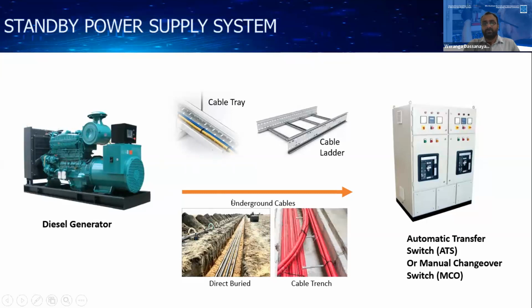same as before in the medium voltage system, the cable may go through a cable tray, cable ladder, or an underground cable. Then it comes to an automatic transfer switch or manual changeover switch. I think if you have visited some larger scale buildings, you can see this kind of installation. Mainly, most of those buildings have a room called the electrical room. If you visit this electrical room, you can see and identify these components clearly.